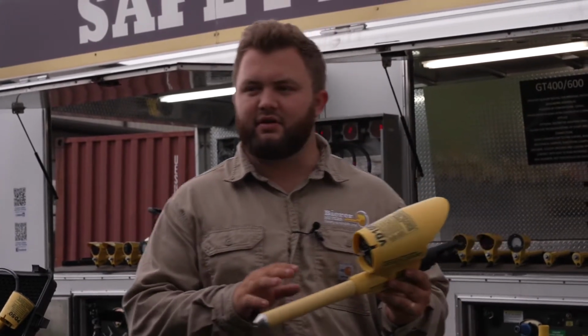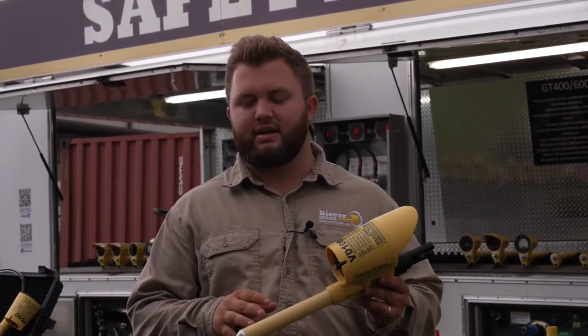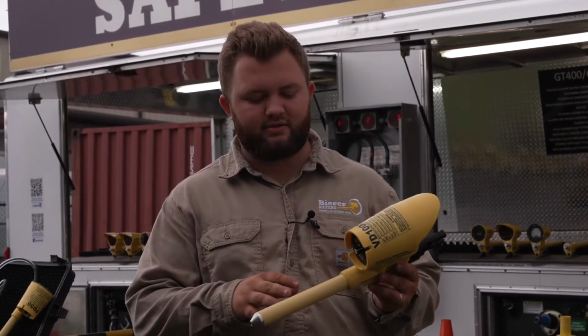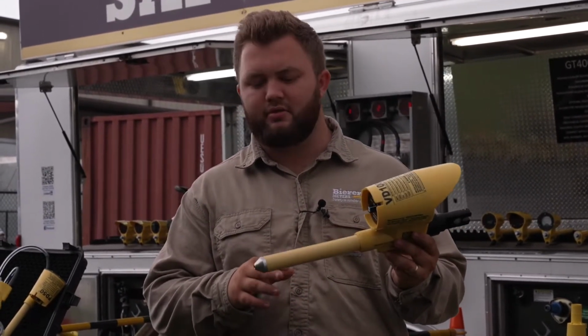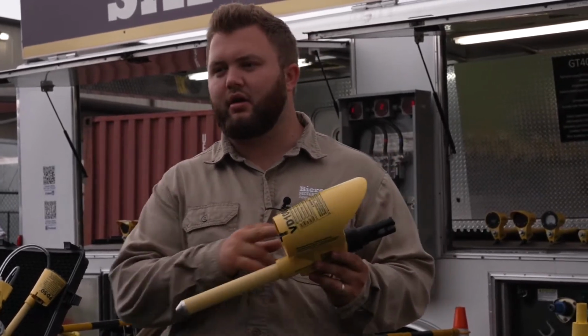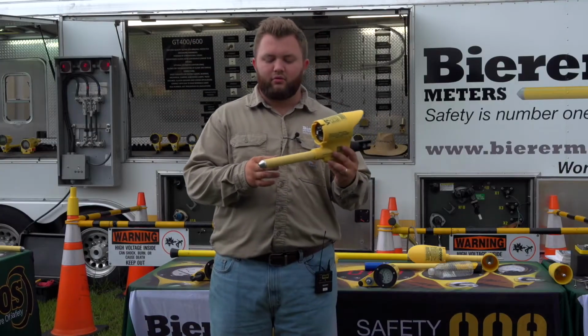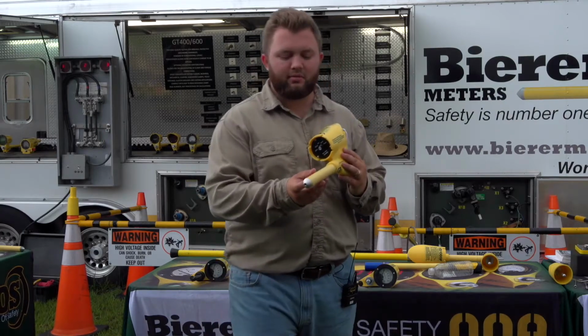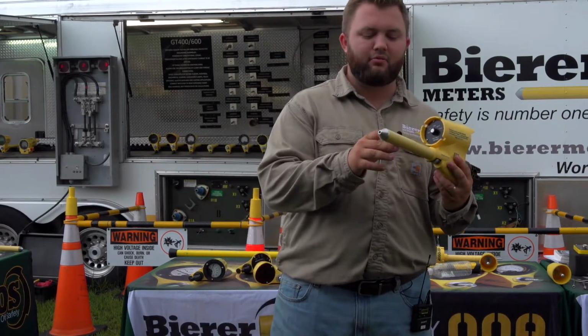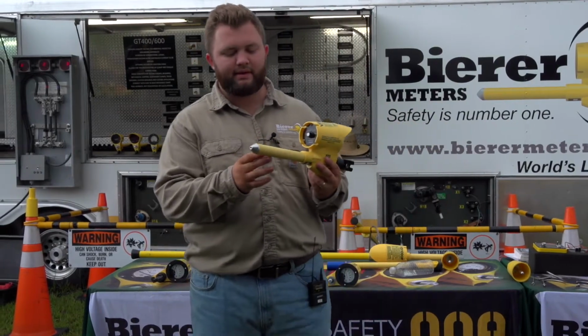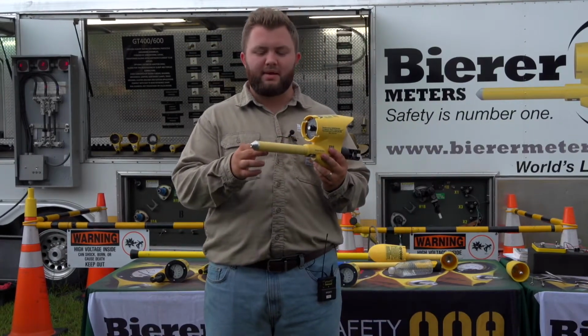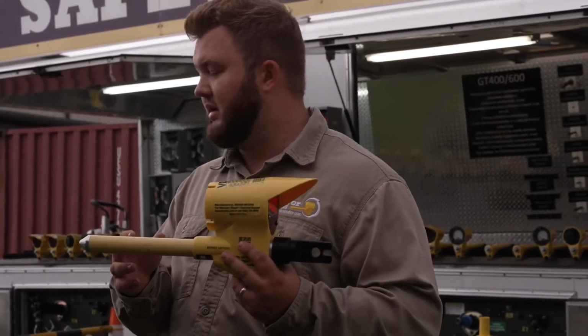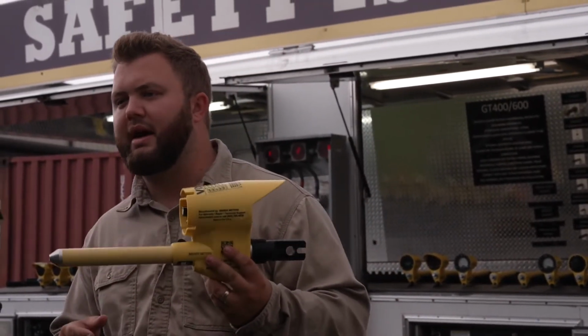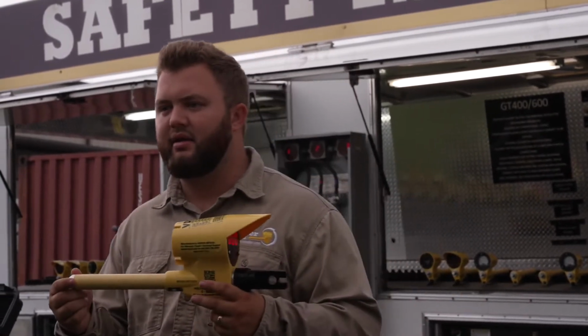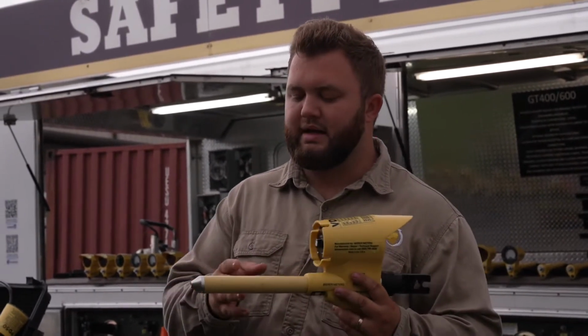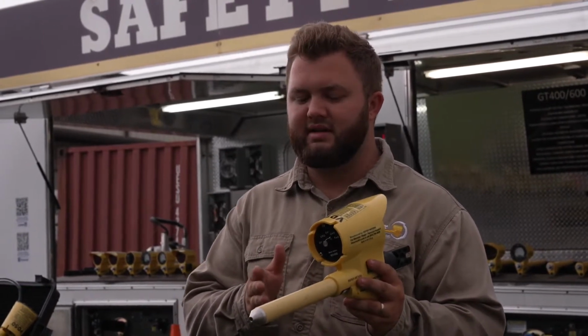So what you could experience if you're using the tool improperly, or if it's dirty, it's got improper calibration stickers, maybe the tool's being misused, is an external arc across the device. What we put on the device here is a line limiting mark. That line limiting mark is a recommendation by ASTM. You don't want to bypass it on this stem with a conductor, an energized source, or a nearby ground, especially if you're making contact here with an energized source and there's a ground in close proximity to this device.